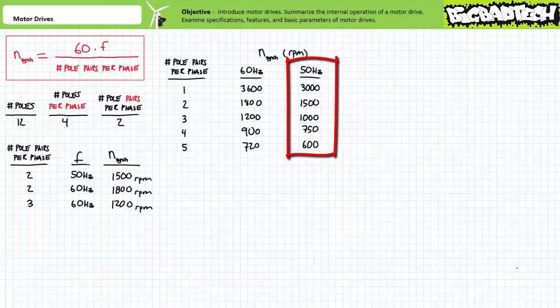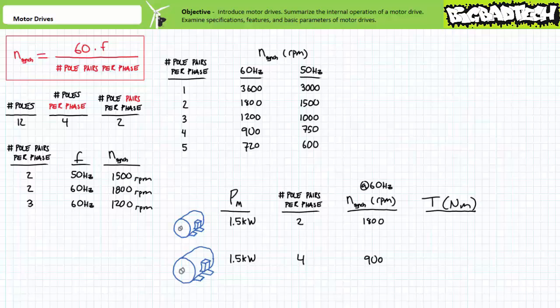In the EU, one would typically experience motors running at 3000, 1500, 1000, 750, 600 RPM, and so on. It should be noted that increasing the number of pole pairs per phase increases the physical size of a similarly rated motor. For example, a 1.5-kilowatt motor with four pole pairs per phase might be twice as big and heavy as a 1.5-kilowatt motor with only two pole pairs per phase.